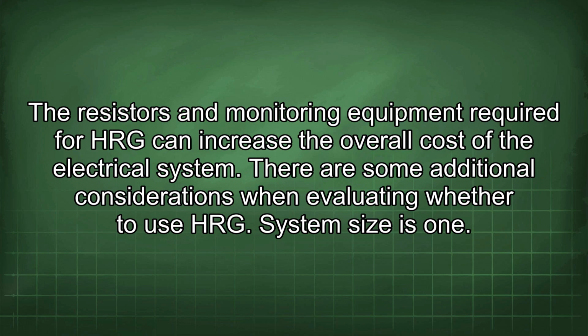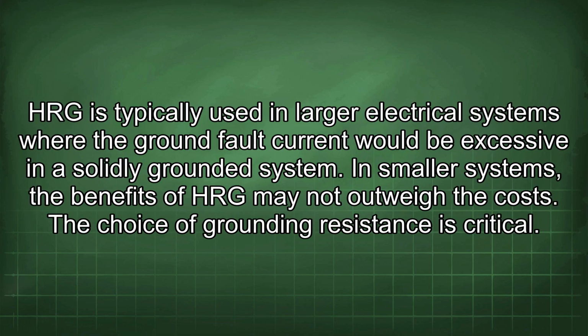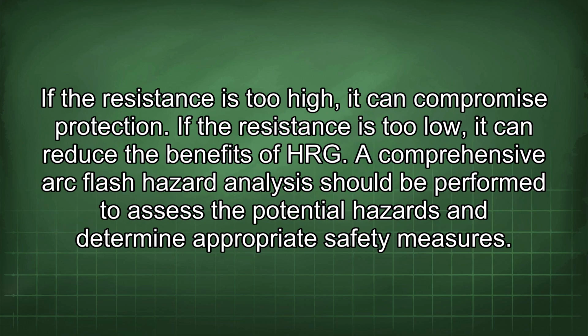There are some additional considerations when evaluating whether to use HRG. System size is one. HRG is typically used in larger electrical systems where the ground fault current would be excessive in a solidly grounded system. In smaller systems, the benefits of HRG may not outweigh the costs. The choice of grounding resistance is critical. If the resistance is too high, it can compromise protection. If the resistance is too low, it can reduce the benefits of HRG.